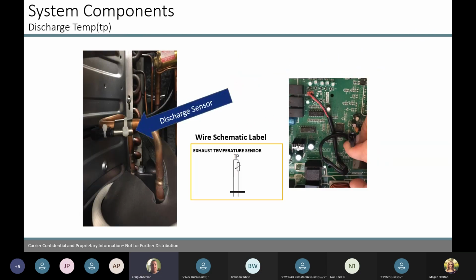Discharge temperature sensor. So this one here works along with your low pressure switch. Because these units, when they turn on, they turn on so low and then they ramp themselves up. So our low pressure switch is set so low because of the smooth operation of the compressor and how low it is starting. So this discharge sensor is helping the low pressure switch out. So it's a loss of gas sensor, let's put it that way. If there's no gas in the unit and the unit starts, the sensor is going to activate before the low pressure sensor. So it's just a backup, they work together.